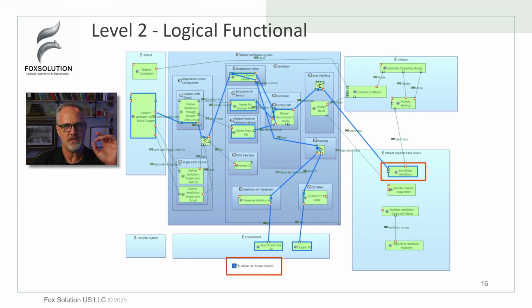And one of the things that you need to think about is when we do usability engineering, what we're doing is we're looking at this function that's delivered by a person and the place in the system that it's being delivered to, and we're assuring that the function that we think the user is delivering is actually going to give us the expected feedback to the system at the user interface in the system, whatever the user interface is, whether it's a touch screen or buttons or whatever. So this provides us with a really nice map of what to analyze when we're going into this usability analysis.